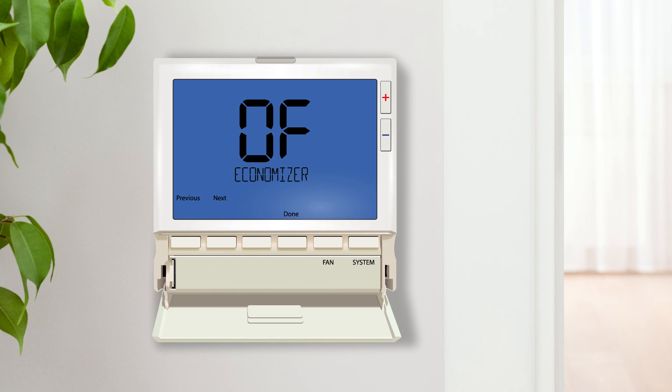Economizer mode enables the thermostat to operate an economizer during the wake, return, sleep and occupied time periods. Once selected, an additional setting will follow to choose the configurable terminal. This setting requires a 7-day or 5-1-1 program and cannot be used with other advanced settings.